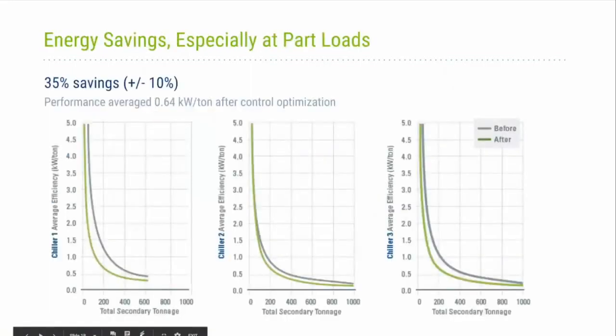And this is some of the data. Again, roughly 35% savings at the chill water plant. This is not whole building savings. This was based on the comparison of the simulated period of 2 weeks in March and 2 weeks in August to the other 6+ months of optimized performance. So an average of about 0.6465 kW per ton, which is actually very good.